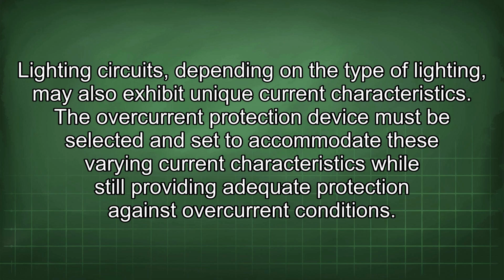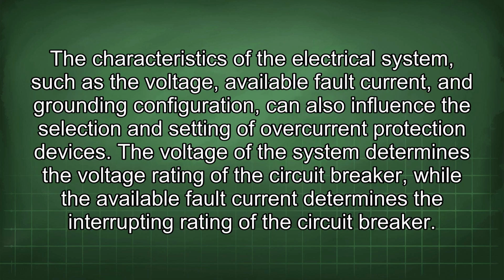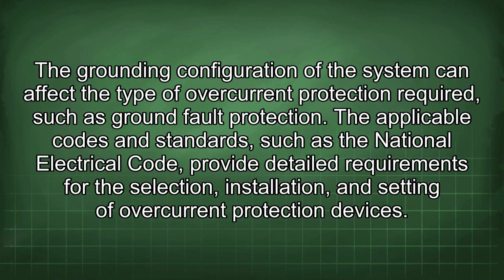The overcurrent protection device must be selected and set to accommodate these varying current characteristics while still providing adequate protection against overcurrent conditions. The characteristics of the electrical system, such as the voltage, available fault current, and grounding configuration, can also influence the selection and setting of overcurrent protection devices. The voltage of the system determines the voltage rating of the circuit breaker, while the available fault current determines the interrupting rating of the circuit breaker. The grounding configuration of the system can affect the type of overcurrent protection required, such as ground fault protection.